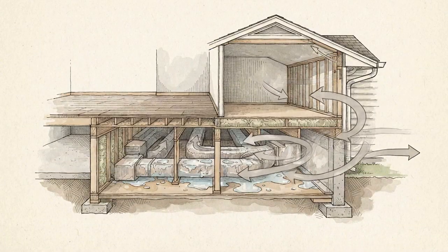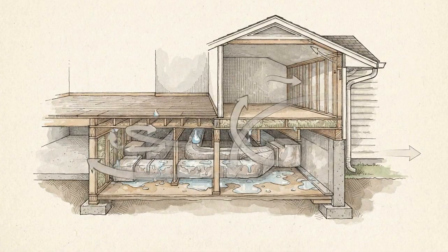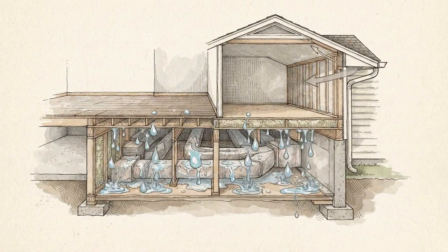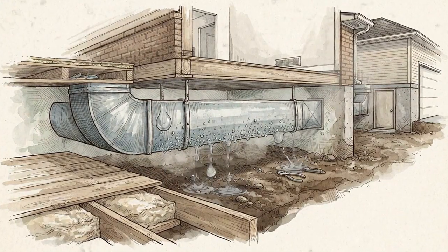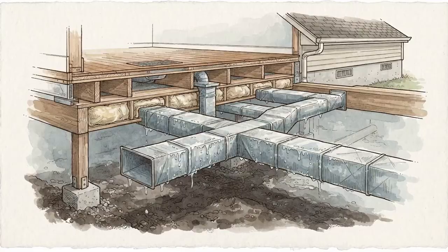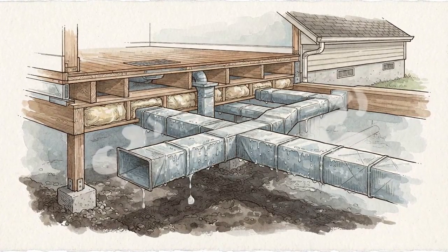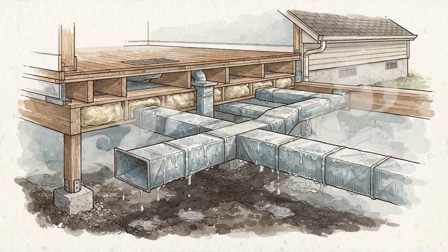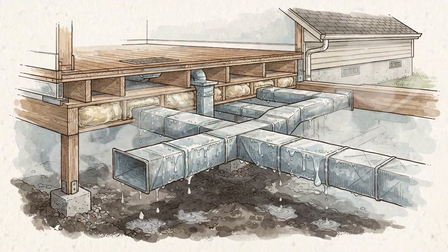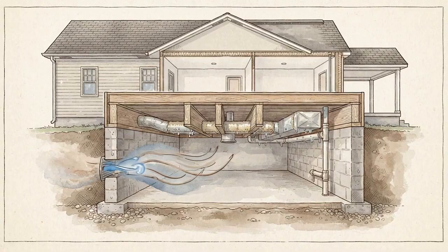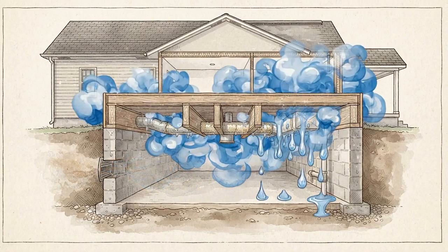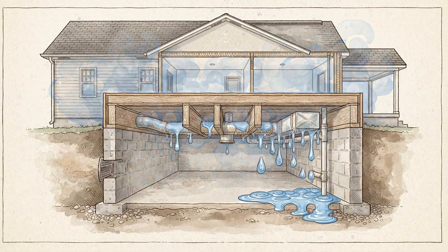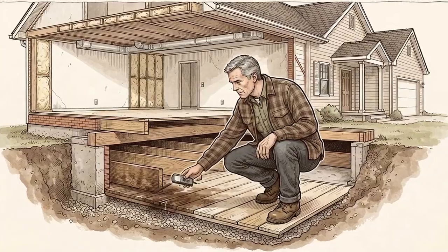Every parcel of air has a fixed dew point that depends entirely on how much water vapor it contains, regardless of how warm or cold the air itself is. When you cool that air below its dew point, the water condenses out onto any surface it encounters. On a humid August morning, the outside air might be 83 degrees Fahrenheit, with a relative humidity of 75%.